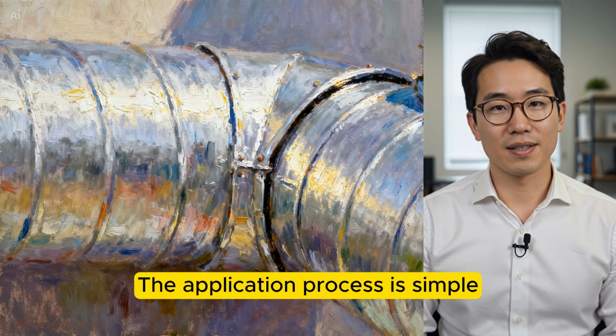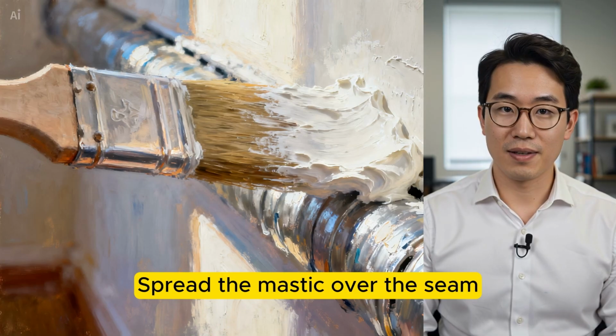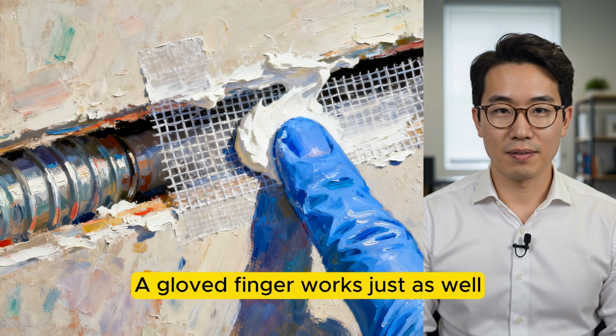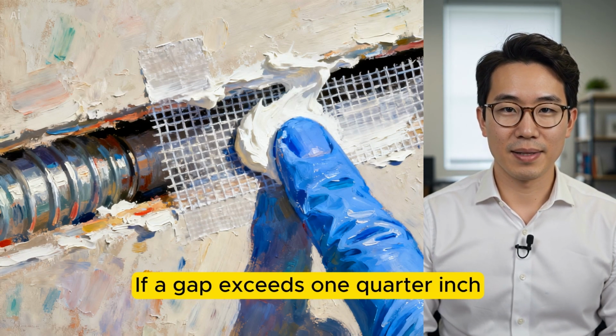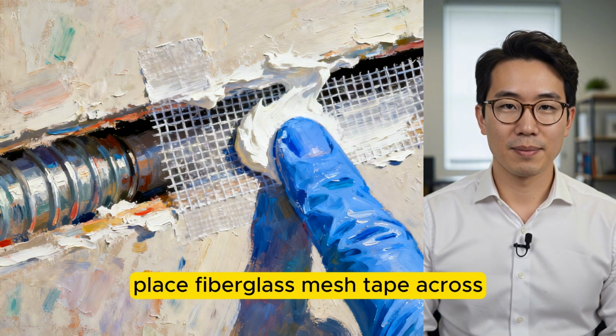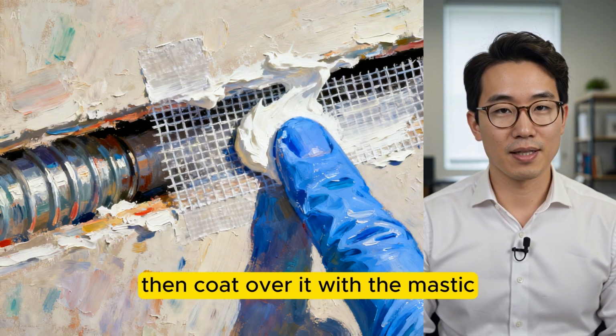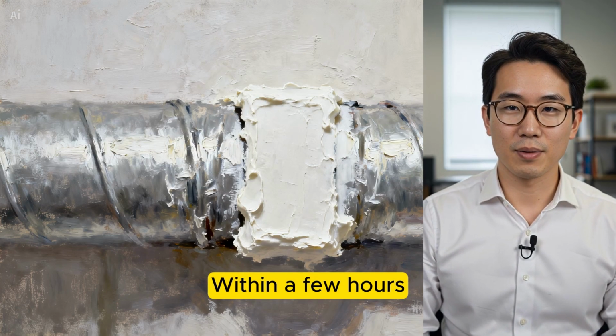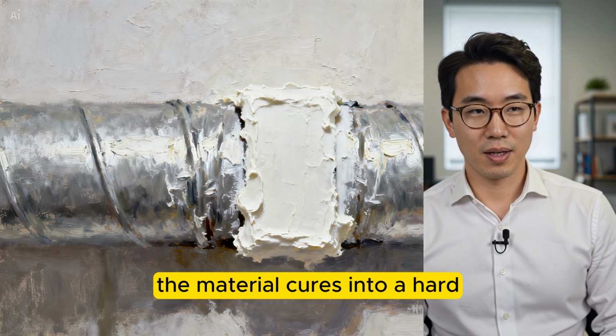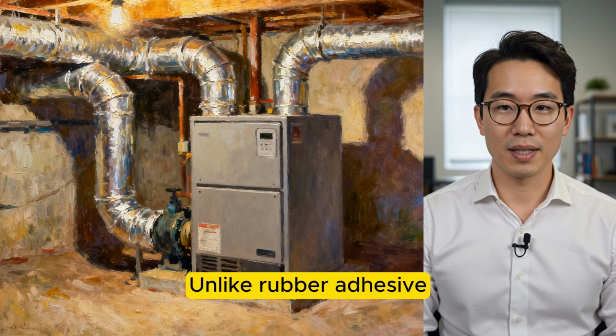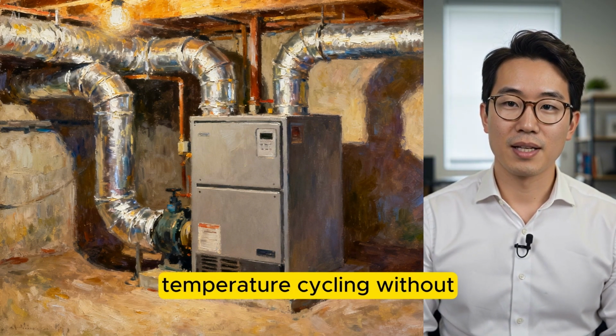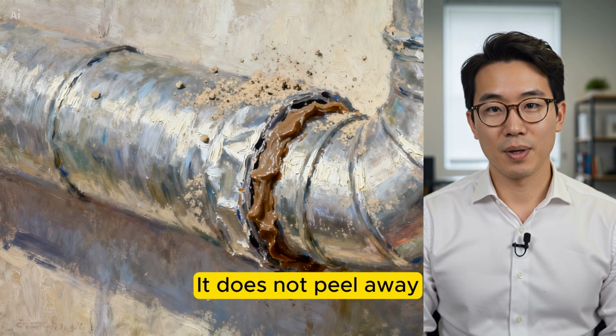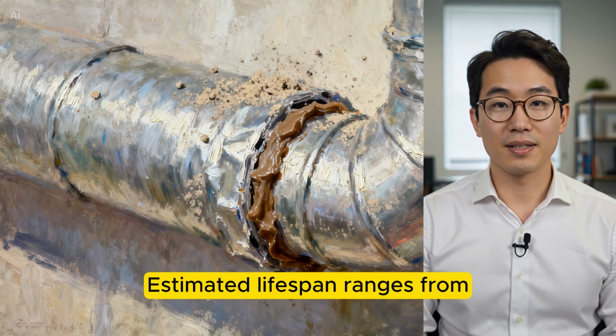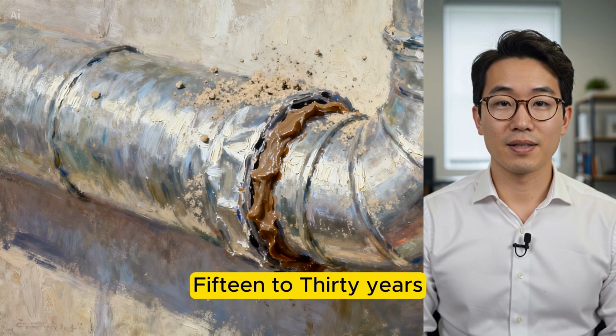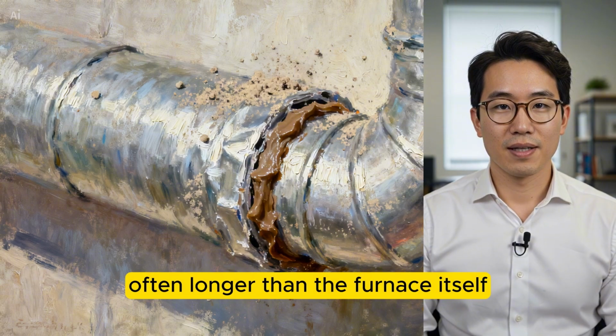The application process is simple. Spread the mastic over the seam using a disposable paintbrush. A gloved finger works just as well. If a gap exceeds 1/4 inch, place fiberglass mesh tape across the opening first, then coat over it with the mastic. Within a few hours, the material cures into a hard but flexible seal. Unlike rubber adhesive, it survives constant temperature cycling without degrading. It does not peel away, it does not curl. Estimated lifespan ranges from 15 to 30 years, often longer than the furnace itself.